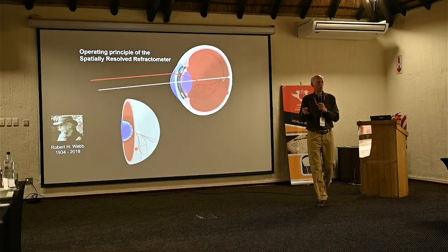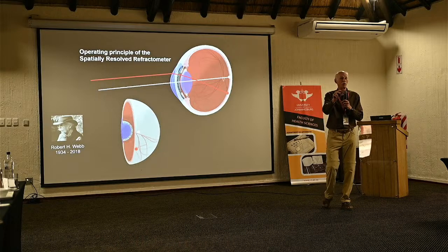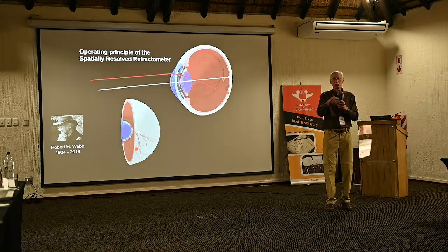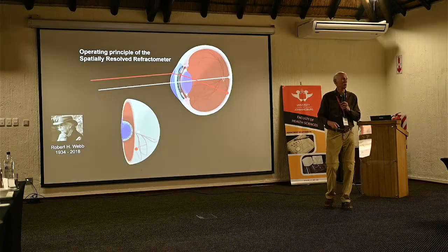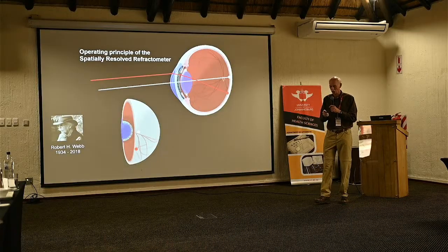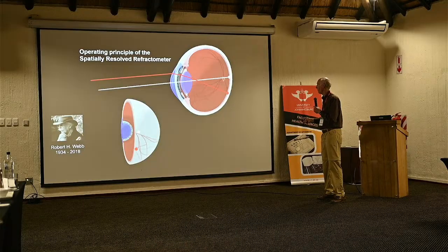There was a glass sphere, etched at the edge to make it scatter light a little bit, and then put it into our aberrometer, made the aberrometer do its thing, and you can see the little dot moving all around the backside. It was a nice little toy that showed us that the instrument was working as it was supposed to be. It was a scanning aberrometer.